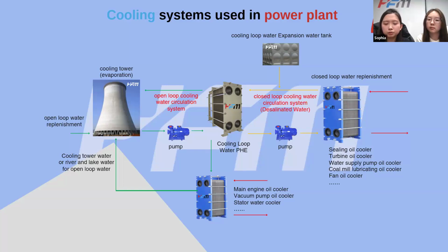As for the closed loop cooling water circulation system, the water has been desalinated and is circulated through the pump and the plate heat exchanger to regulate the temperature of the equipment. In this system, there's also a water replenishment section to ensure sufficient water. In addition, different coolers are used to cool the oil and water of the various equipment of the power plant, including the main engine oil cooler, vacuum pump oil cooler, stator water cooler, and others. These cooling systems and equipment work in tandem to ensure the efficient and safe operation of the equipment in the power plant.